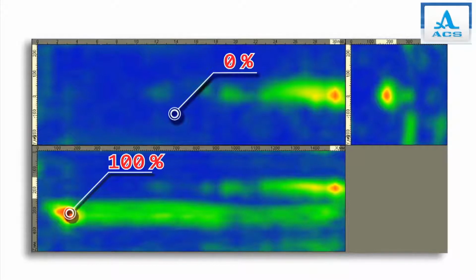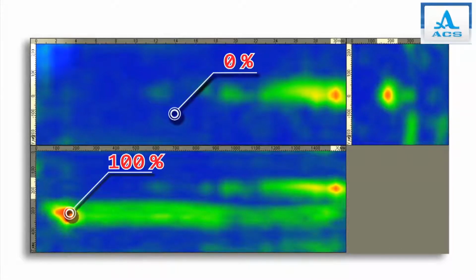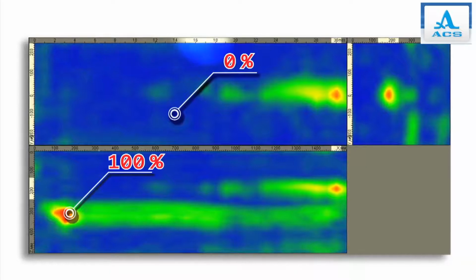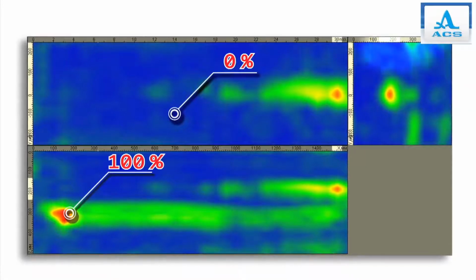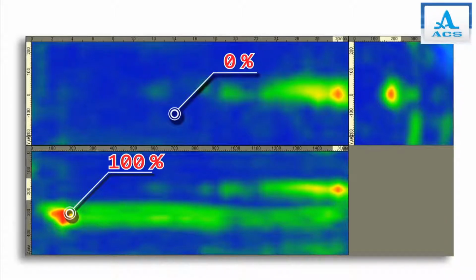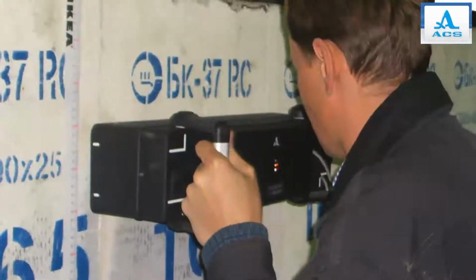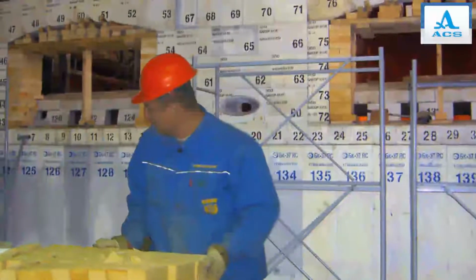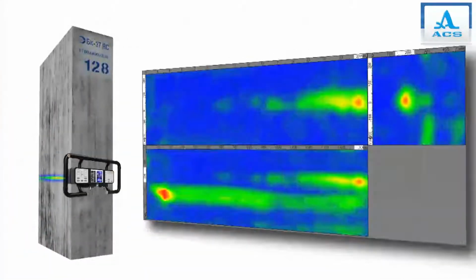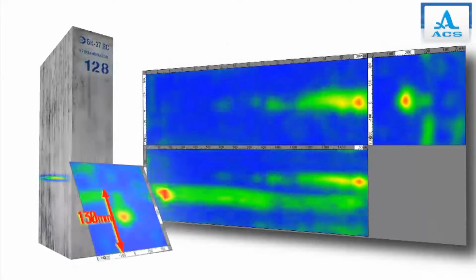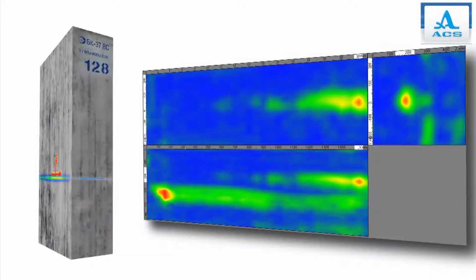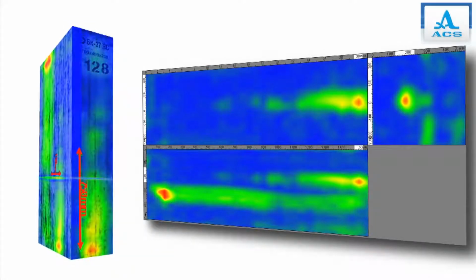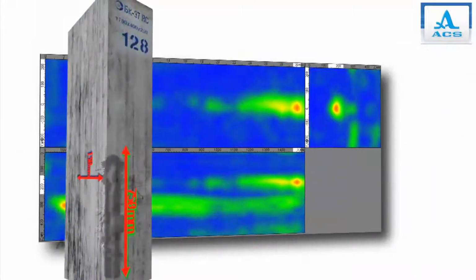The image showing the internal characteristics of the test sample is visualized as a perspicuous color map. Every point in the zone of testing is depicted as a certain color scale, depending on the intensity of its reflection. Every reflector's position can be located with a high degree of accuracy. The tomogram shown was obtained from tests performed on fireproof plates of a glass melter. At a nominal depth of 130 millimeters from the surface, a cylindrical-shaped flaw, approximately 750 millimeters long, can be observed.